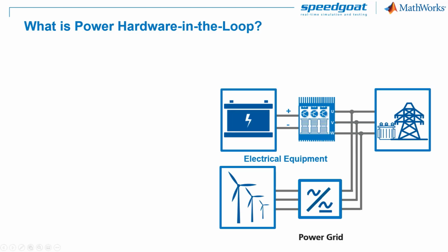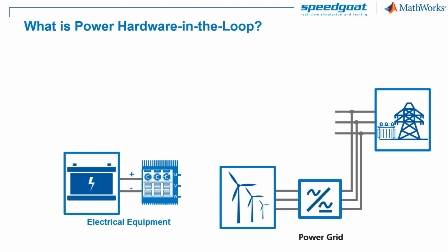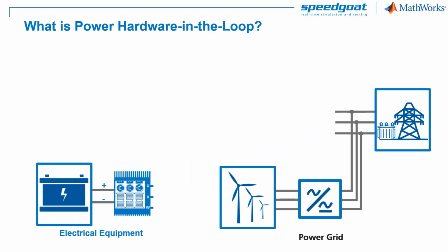One accepted testing methodology is power hardware in the loop. We will first isolate the electrical equipment that we want to test from the rest of the electric grid. We call the electrical equipment EUT, that stands for Equipment Under Test, and the rest of the electric grid is referred to as ROS, that stands for Rest of System.